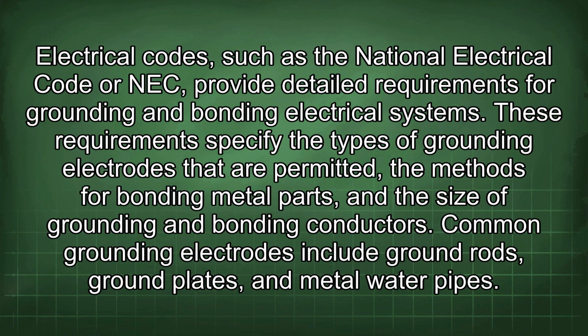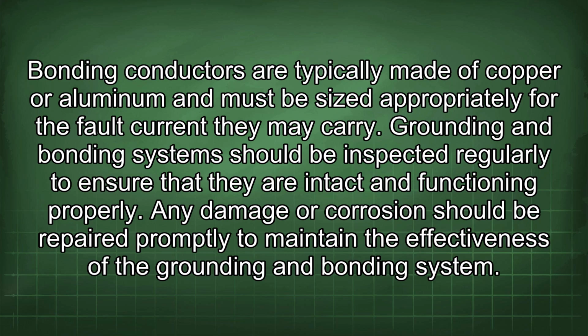Electrical codes, such as the National Electrical Code or NEC, provide detailed requirements for grounding and bonding electrical systems. These requirements specify the types of grounding electrodes that are permitted, the methods for bonding metal parts, and the size of grounding and bonding conductors. Common grounding electrodes include ground rods, ground plates, and metal water pipes. Bonding conductors are typically made of copper or aluminum and must be sized appropriately for the fault current they may carry.